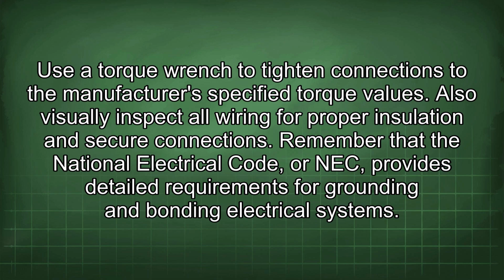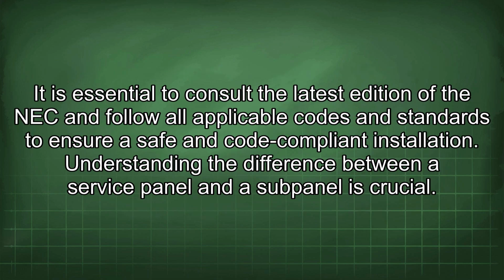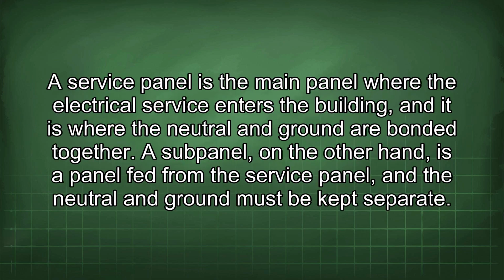Remember that the National Electrical Code, or NEC, provides detailed requirements for grounding and bonding electrical systems. It is essential to consult the latest edition of the NEC and follow all applicable codes and standards to ensure a safe and code-compliant installation. Understanding the difference between a service panel and a subpanel is crucial. A service panel is the main panel where the electrical service enters the building, and it is where the neutral and ground are bonded together.